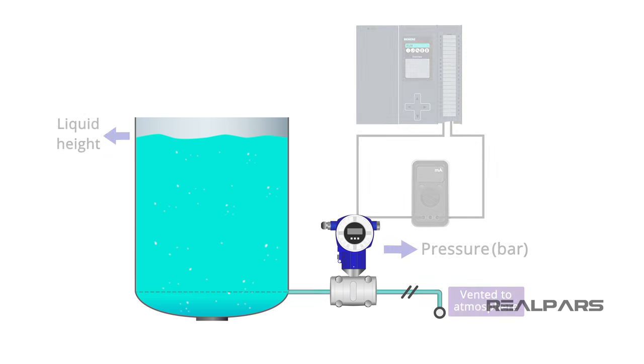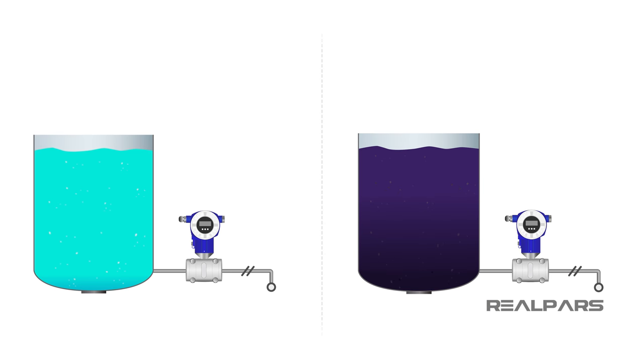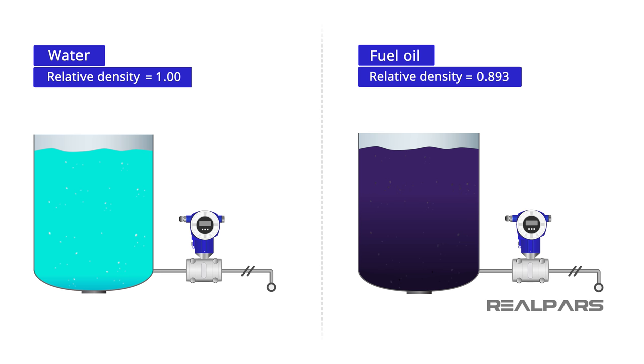We talked about converting the resulting inches of water pressure value into any pressure scale you need, such as psi, kilopascal, or bar. That works just fine if the liquid in the vessel is water. What if the liquid stored in the vessel is not water and doesn't have a relative density of 1?